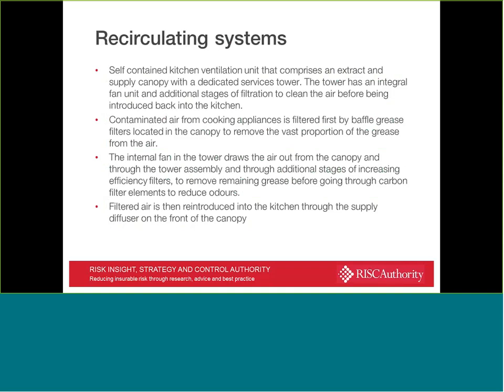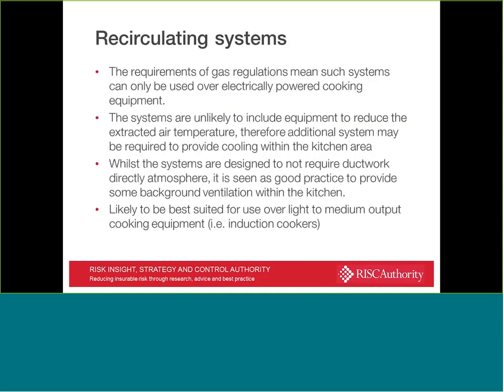The systems use a series of additional filters, so they've got the initial capture of grease and oils, but then there's an additional filtration unit that stands alongside the system that continues, through a series of additional filters, to capture oils and grease. There's a carbon filter at the far end to reduce odours, and then that filtered air can be reintroduced into the kitchen to supply.